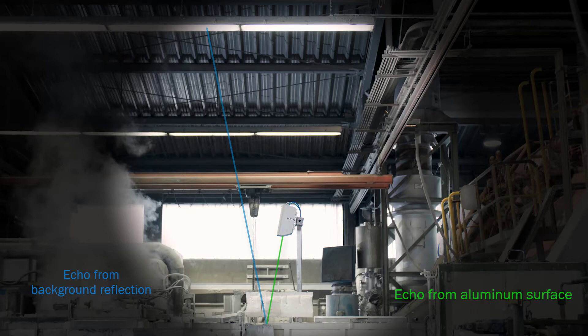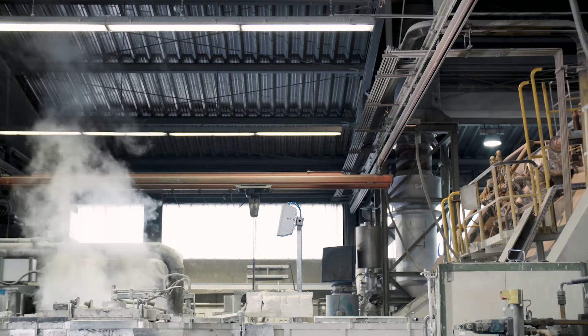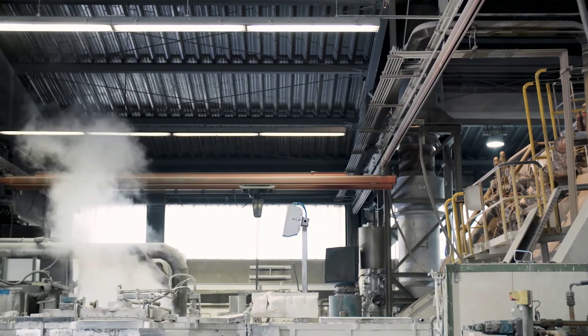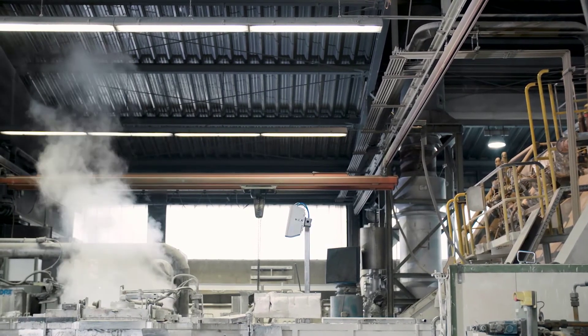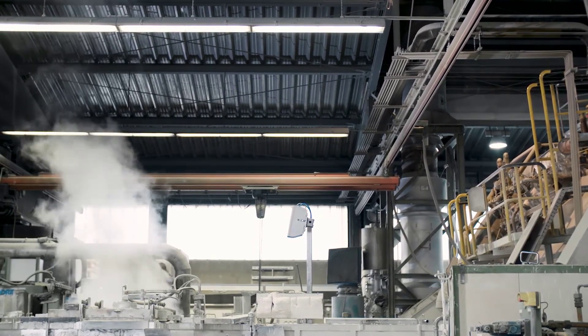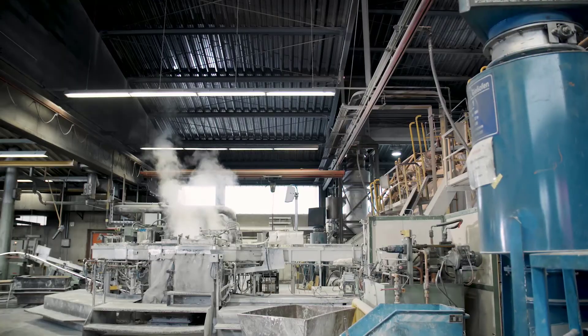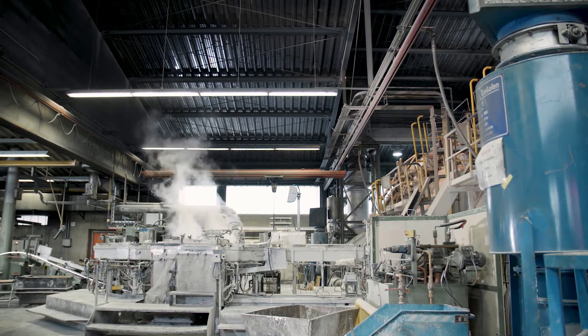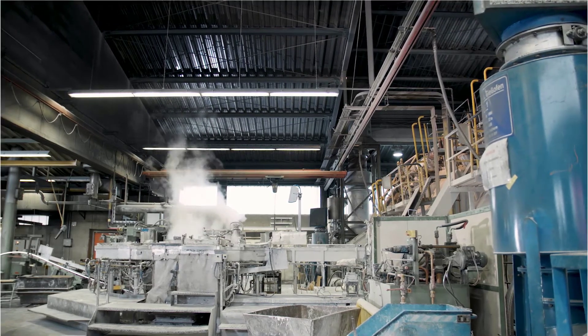In the case of a conventional time-of-flight distance sensor, the simultaneous detection of two echoes usually leads to an error. The multi-echo capability of the HDDM Plus technology makes it possible to separate the relevant echo and the echo from the background reflection.